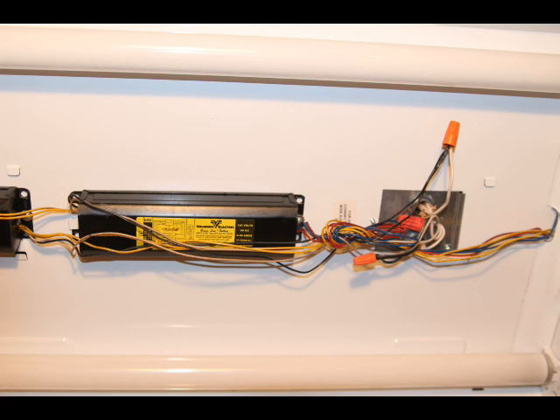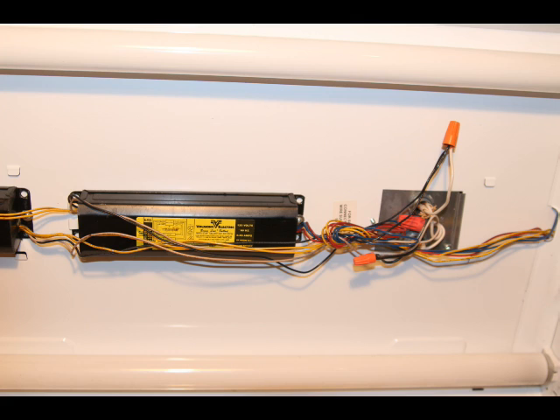This is what the old style ballast looks like. For a four tube fixture, which I have, there will be two ballasts. Each ballast controls a different two tube bank of lights. Each ballast will have a total of eight wires. There will be two yellow wires, two red wires, two blue wires, and a white and black wire.